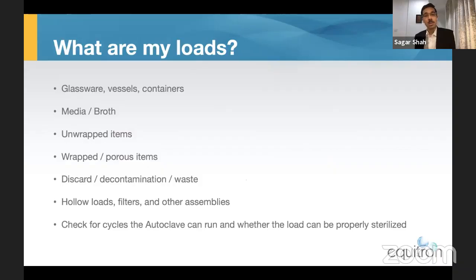But we've seen a lot of clients using non-vacuum autoclaves for some of the more critical loads, such as wrapped or hollow items. Now, that is not recommended because if you need greater sterilization assurance, you should actually be processing such critical items, wrapped or hollow loads, in a vacuum autoclave.